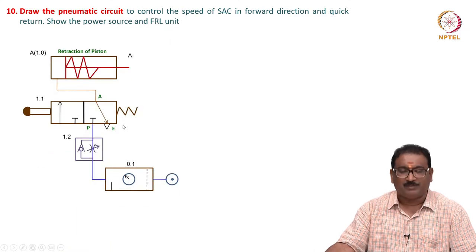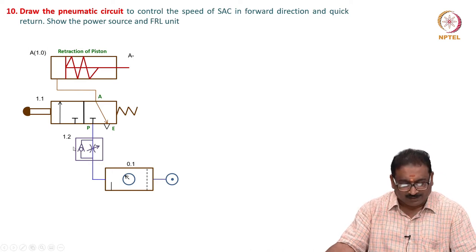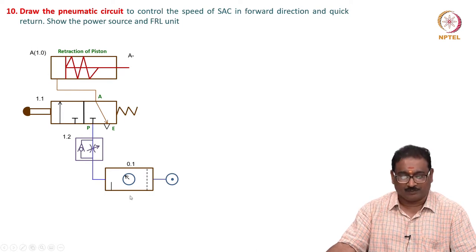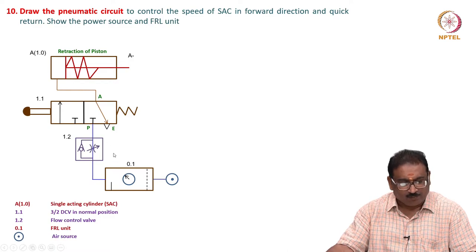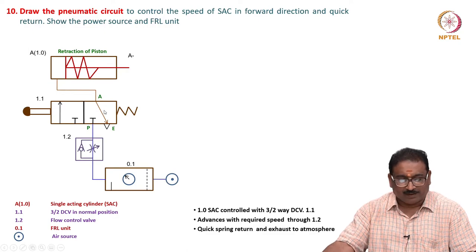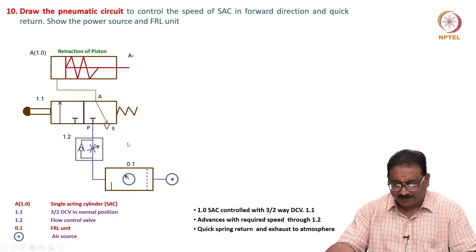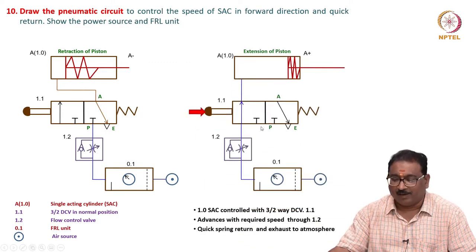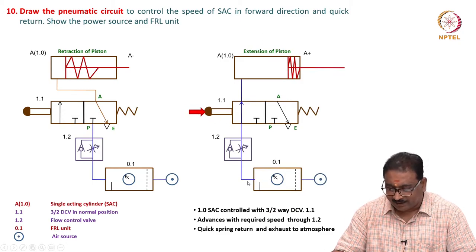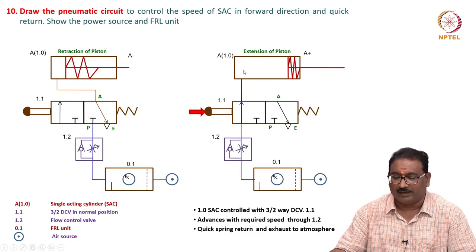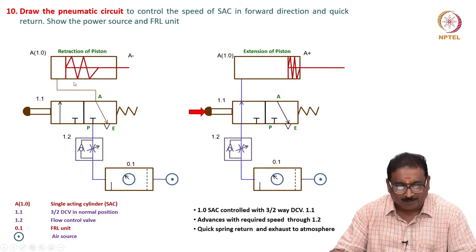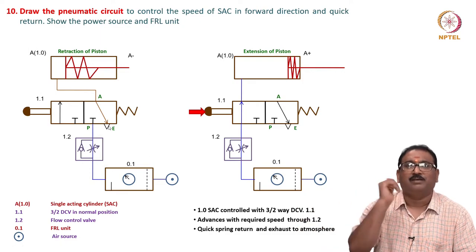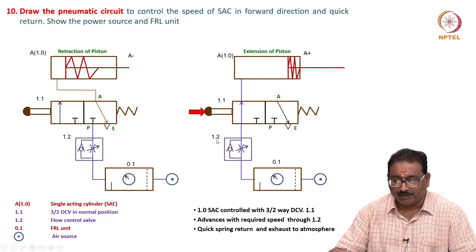Very simple - we have seen these types of problems in hydraulics also. Same thing here - 1.2 is a flow control valve. It is a single-acting cylinder controlled through a 3/2 DCV with power source. The cylinder advances with a required flow rate, controlled through 3/2 DCV 1.1. When you press the button, air comes here, passes through the metered orifice at the required flow rate. Extension is at the required speed. Return is bypass - very quickly it will return. That is why I am placing the flow control valve 1.2 here.